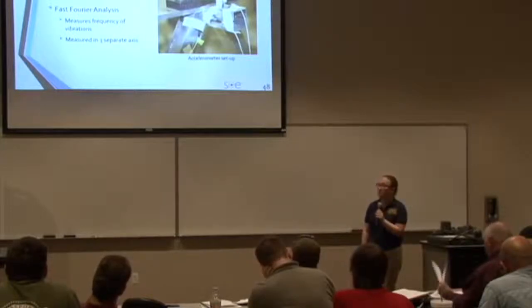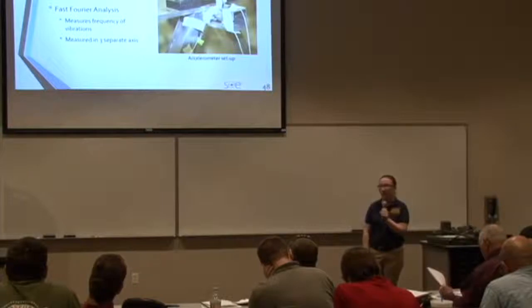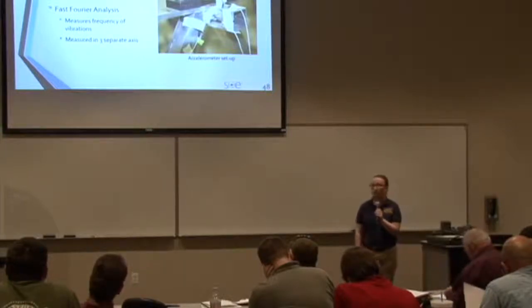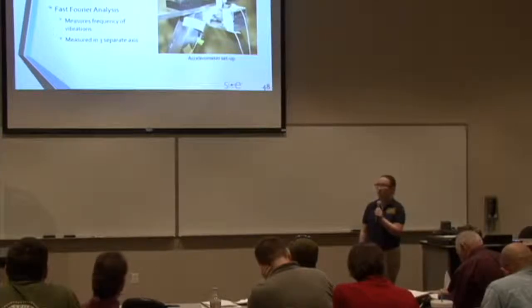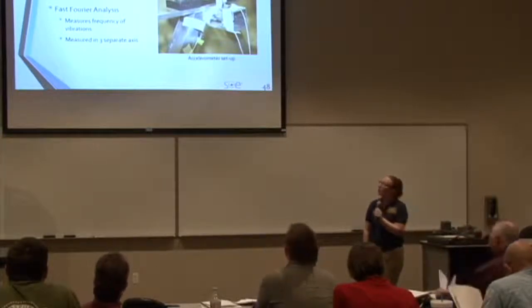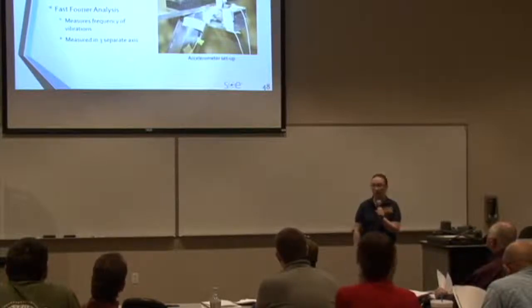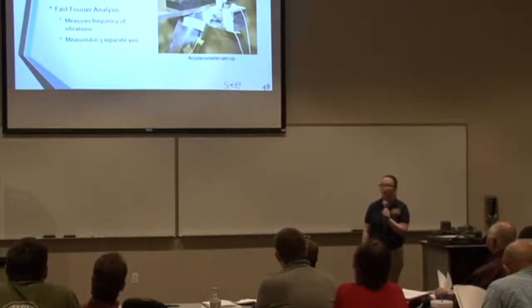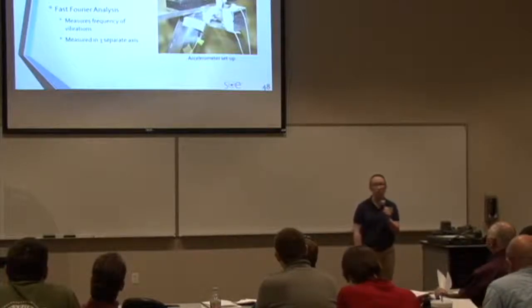We then moved on to do a systems vibration analysis. We used 3 accelerometers borrowed from the S&I lab on campus, and we placed them on IRIS itself, the motor, and then the blower. We placed them in the 3 axes, X, Y, and Z, where the Y axis is the axis parallel to the flow. We were able to do a full speed run of IRIS up to 3200 RPM with no blower, and we analyzed that. And the results we then analyzed using a fast Fourier analysis, which accounts for the magnitude at which the vibrations occurred.